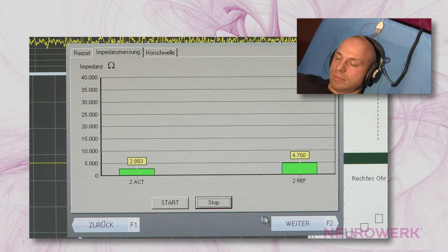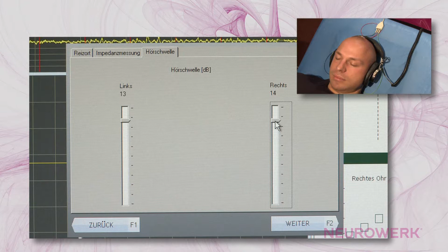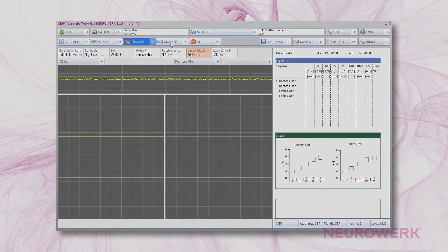The final stimulation intensity for the right and left ear is issued automatically by the Neurowerk EMG after determining the threshold of hearing. The contralateral side is masked with a noise level that is 50 dB above the hearing threshold. The registration of the ABR starts with the analysis feature. For an applicable measurement, the potential is averaged 2000 times.